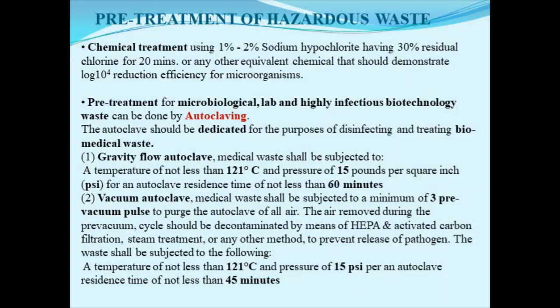It usually takes around 15 to 30 minutes. And after reaching that temperature of 121 degrees Celsius, which is ensured at a pressure of 15 psi, the holding time at that temperature of 121 degrees Celsius should be at least 1 hour. So that is the holding time. So total autoclaving time is around 1 hour 15 minutes to 1 hour 30 minutes. This is very important.